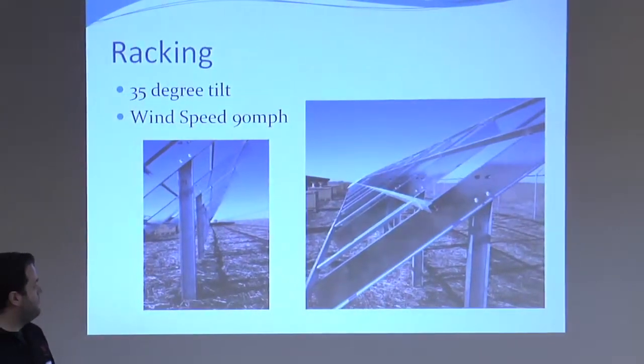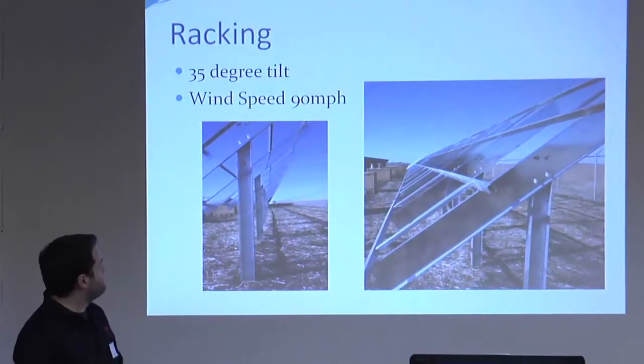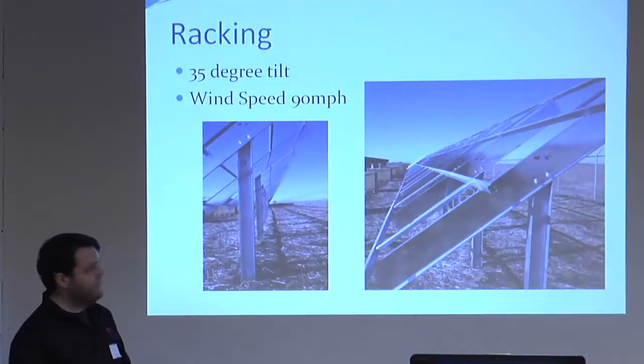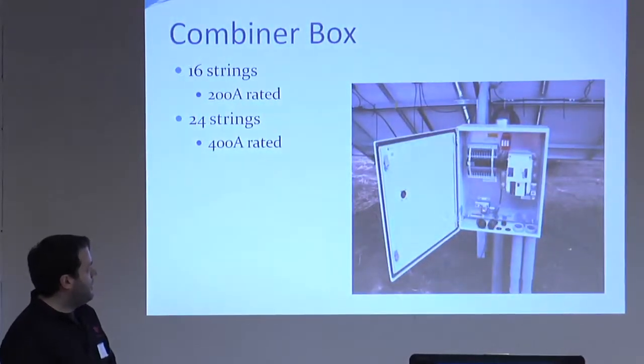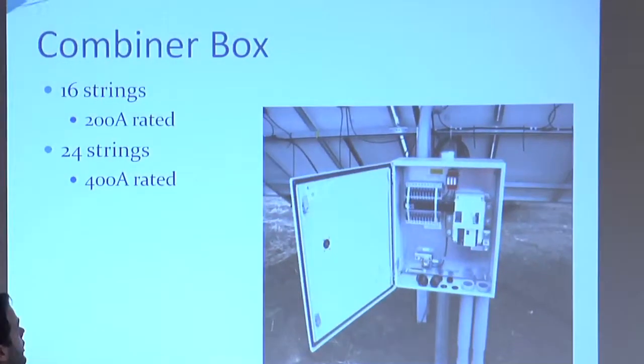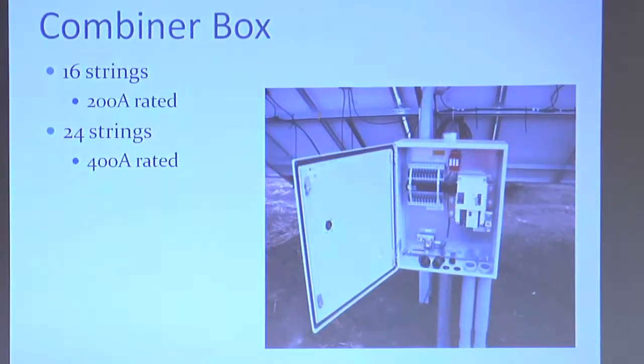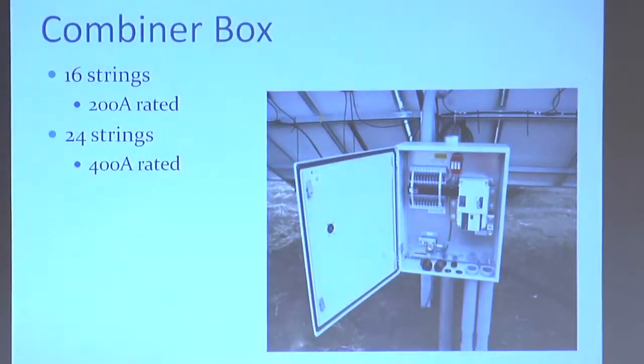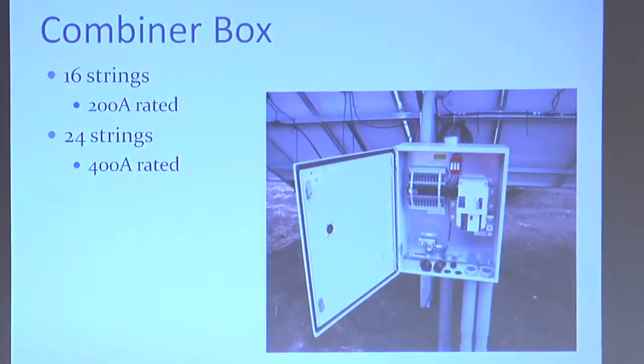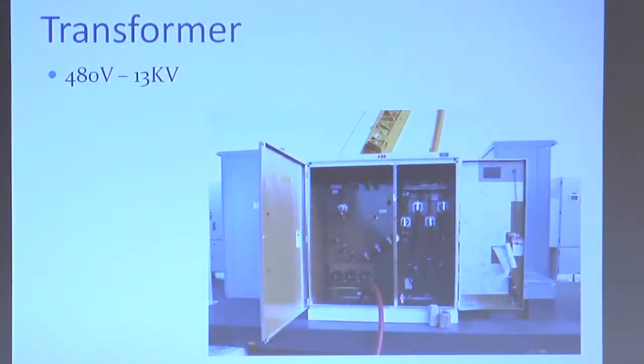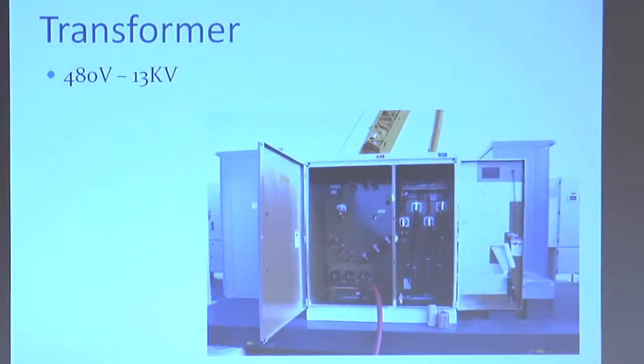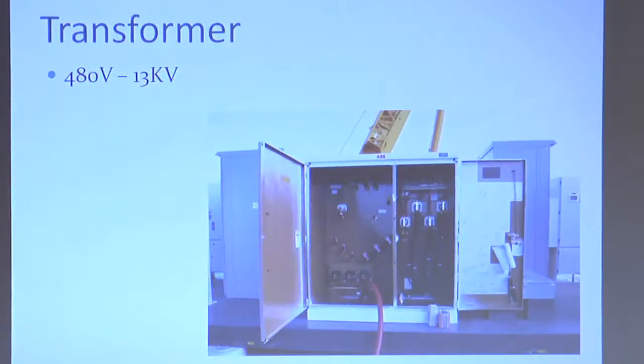The racking, again, is a 35-degree tilt rack, and I'll have a couple of pictures of the installation coming up here. Combiner box, pretty straightforward. We use 16 and 24 string combiner boxes, and I'll show you how those went together. These are disconnecting combiner boxes, so you can walk out to the field and turn off that particular section of the array if you need to. The transformer, as I said, steps up power to interconnection voltage with Xcel Energy. This is a distribution substation, so the power was interconnected at 13 kV.